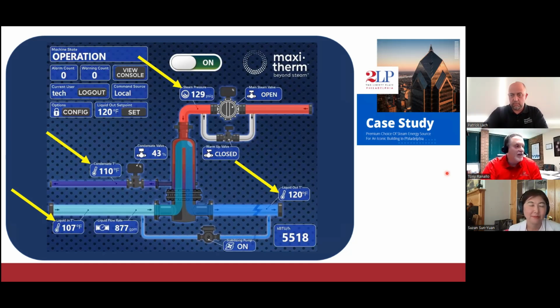You can see in this particular case, we're running at about 43% of the input load, and things are just cooking right along. We also include in our skids a little BTU meter so we can see the actual throughput. Right now we're running at about 5.5 million BTUs through this particular skid at about 877 GPM. So this is a very nice thing. No quencher required. Condensate goes right to drain. We save a lot of energy there.